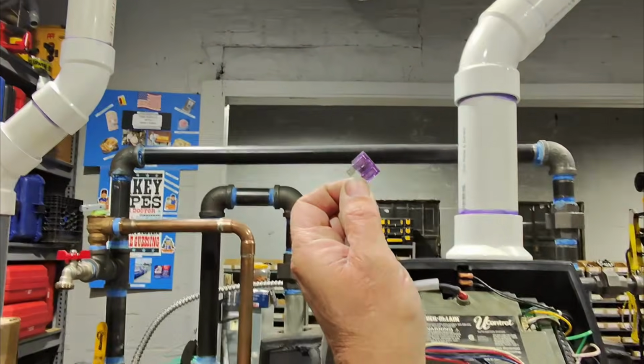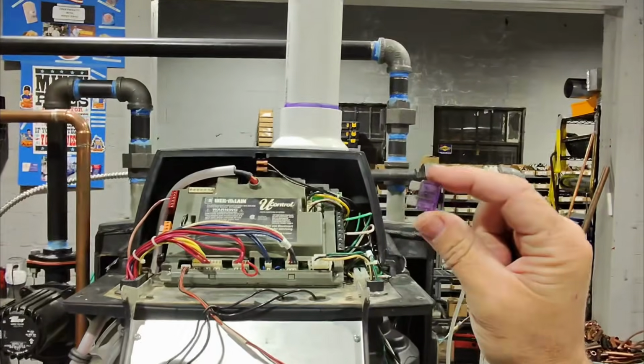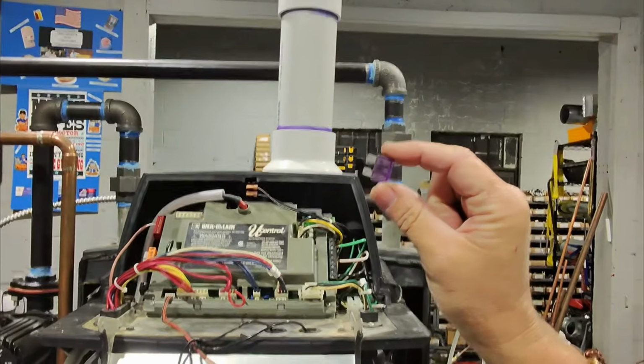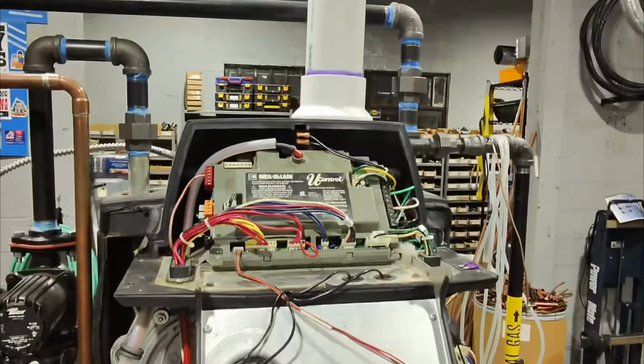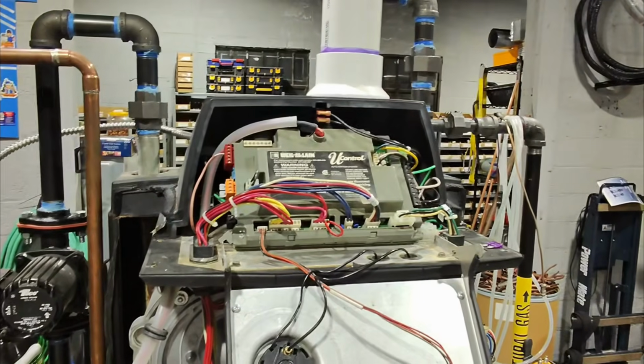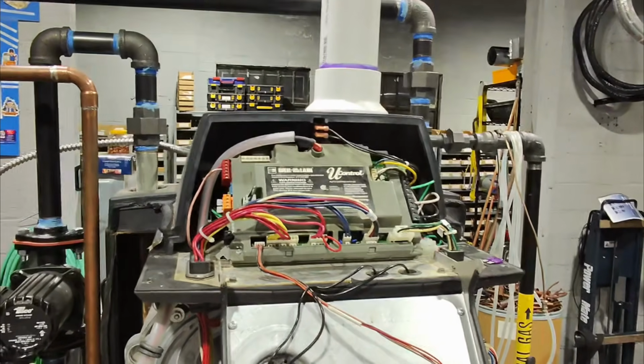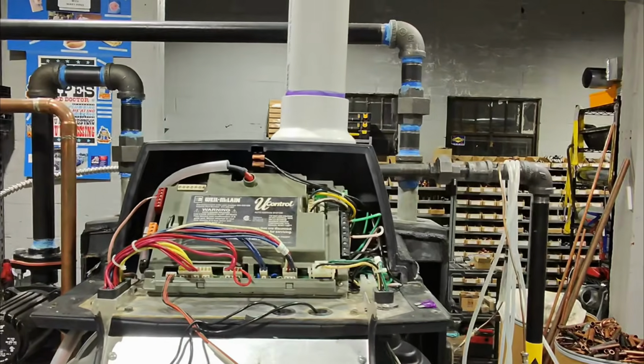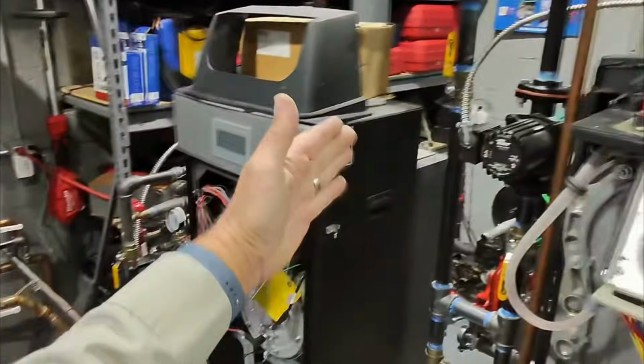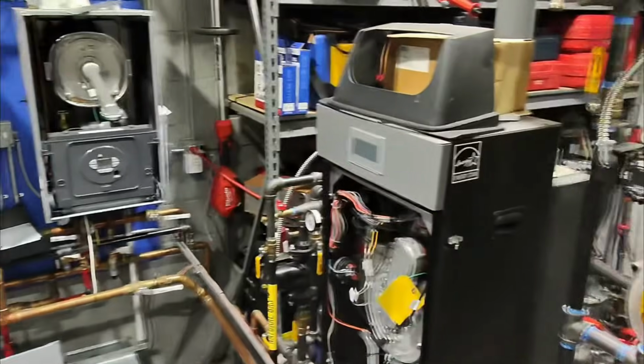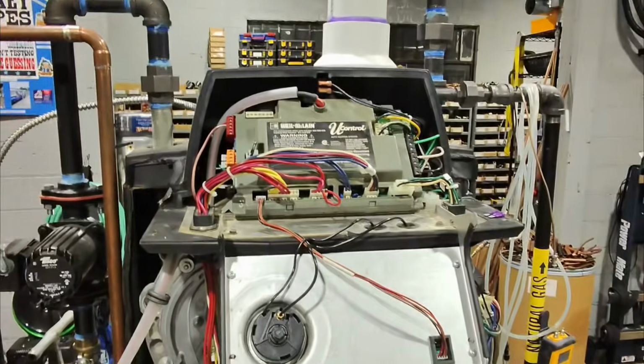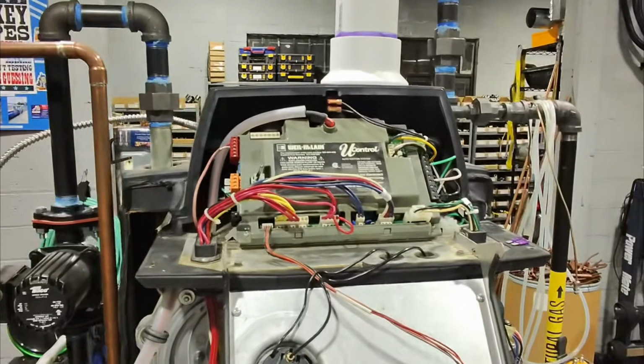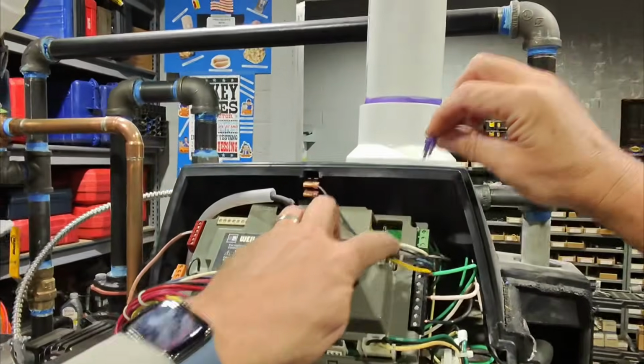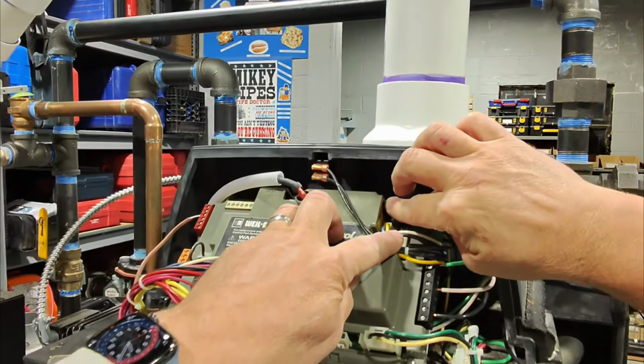Now, why would this be blown? That's the $1,000,000 question. Don't just start replacing fuses. Figure out what the problem is and solve that. In my particular case, we had a short on the low voltage control wiring. I have multiple heating systems here, all connected, and I had 2 accidentally on at the same time, which blew out the fuse on the U-control. I'm going to put a new 3 amp fuse in there.